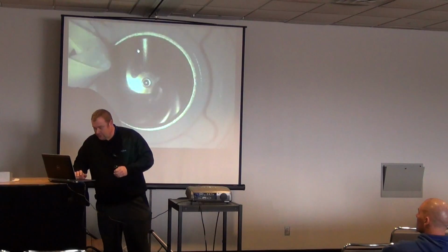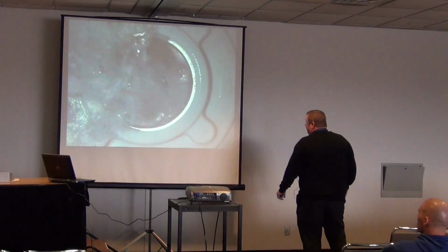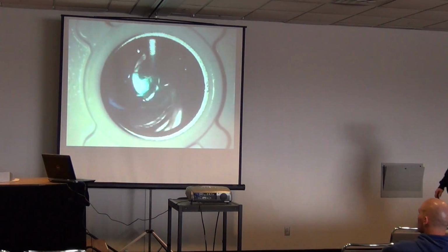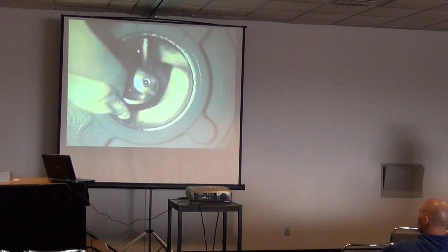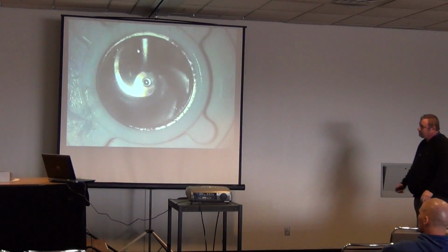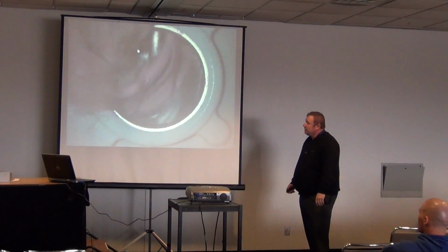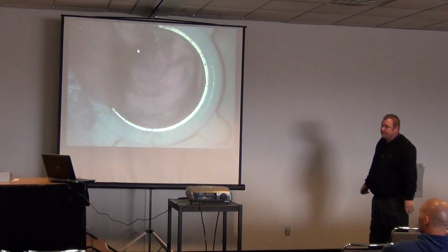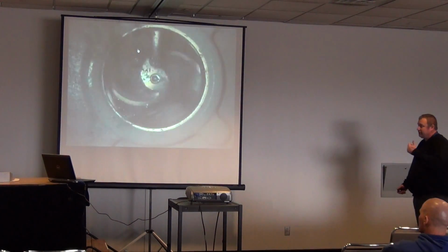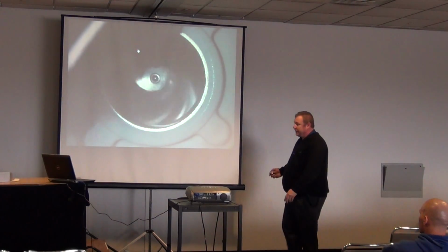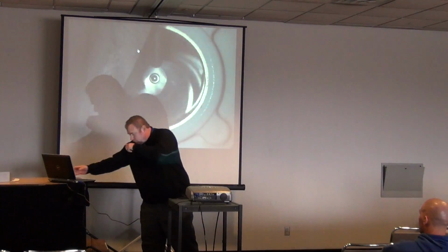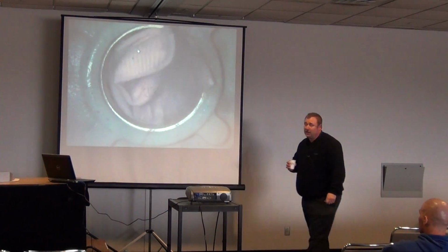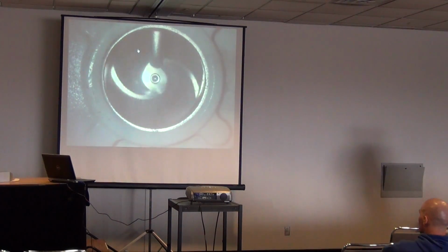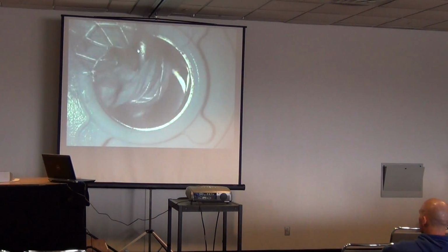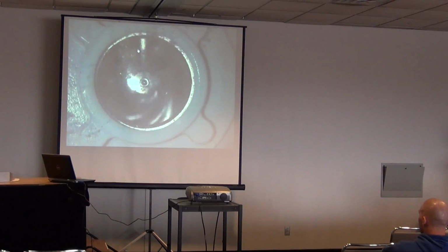So I don't know if any of you passed through our booth yesterday, but here's an example of the wet end of the N-impeller and what that can really do with those kinds of materials. So these were R&D tests in the Flygt factory in Sweden, showing wet tex items, towels, bottles, things of that nature going through this pump. That pump there, that test is being done on a model 3127, which is roughly a 10 horsepower pump. So that just gives you an idea of the types of materials that can pass.